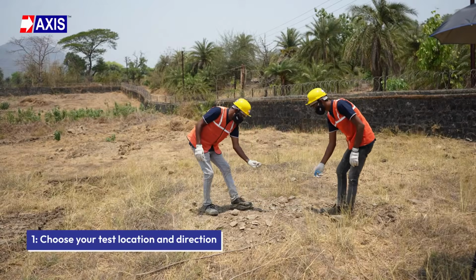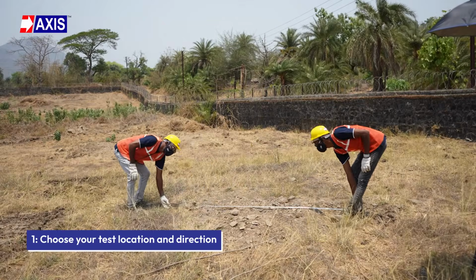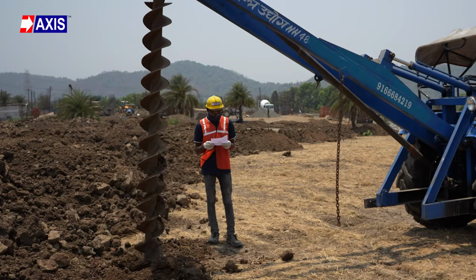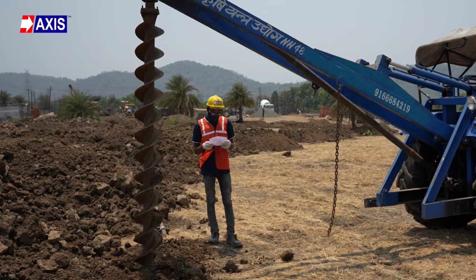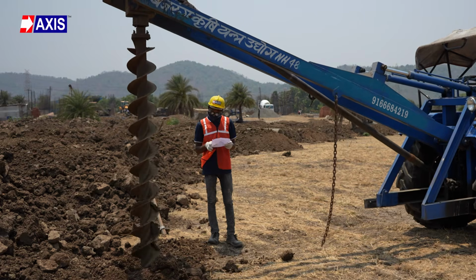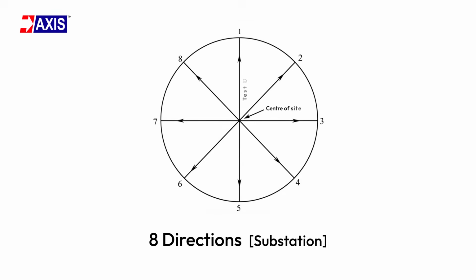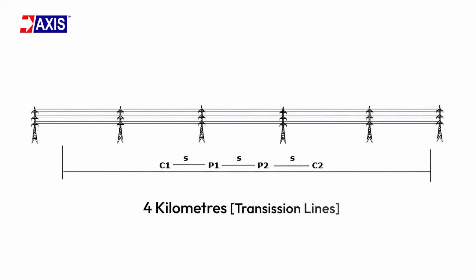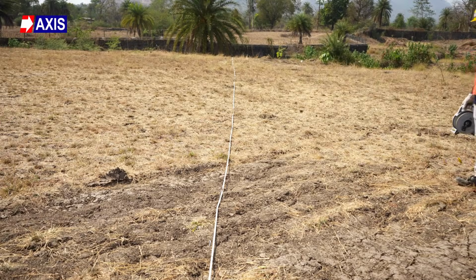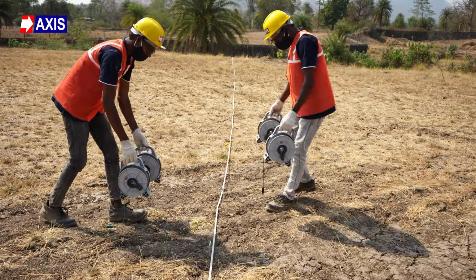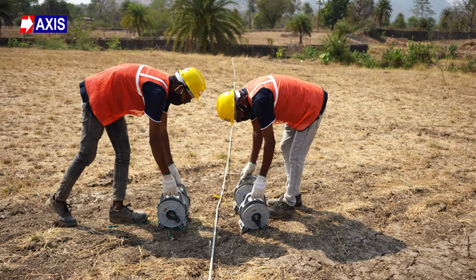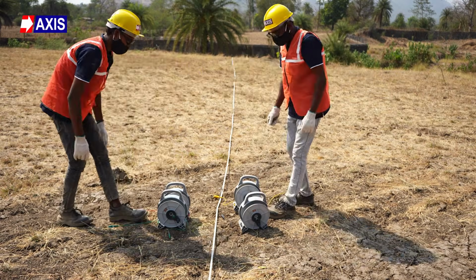Step 1. Choose your test location and direction. The number of test locations depends on the size and type of your site. For example, substations require at least 8 test directions from the center of the site, and for transmission lines, measurements are taken along the direction of the line approximately once every 4 kilometers. In this video, we are demonstrating the resistivity measurement procedure at our manufacturing facility.